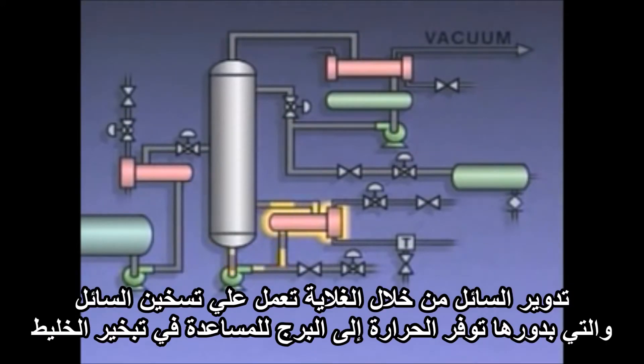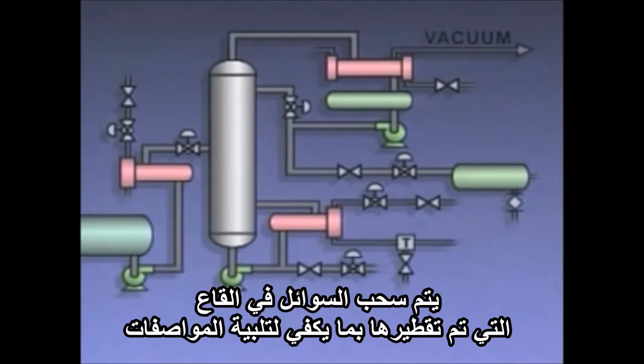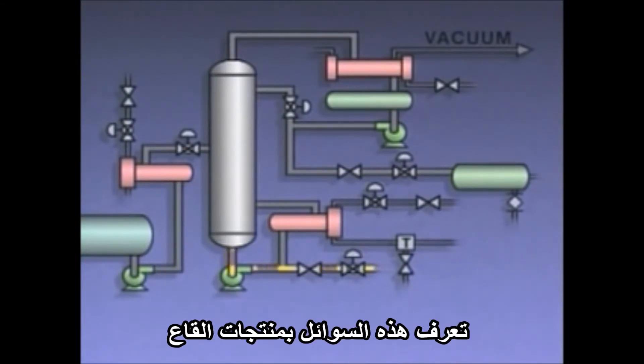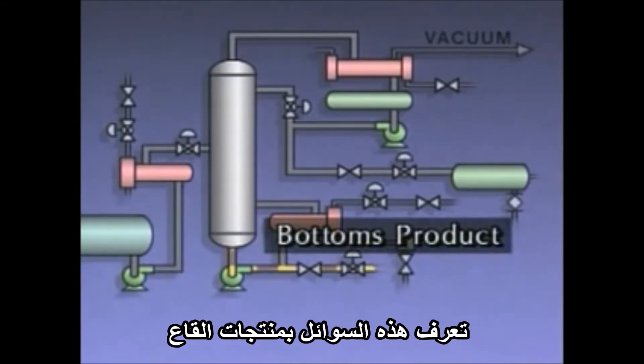Part of that liquid is circulated through a reboiler and back into the column. Circulating the liquid through the reboiler heats the liquid, which in turn provides heat to the column to help vaporize the mixture. Bottoms liquid that's been distilled enough to meet specifications is drawn off through a takeoff line. This liquid is known as the bottoms product.